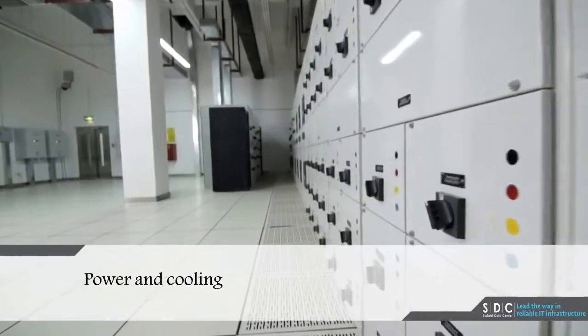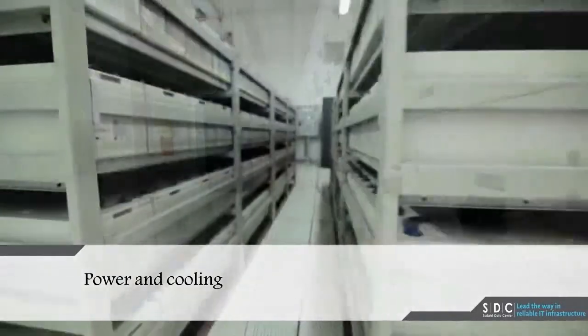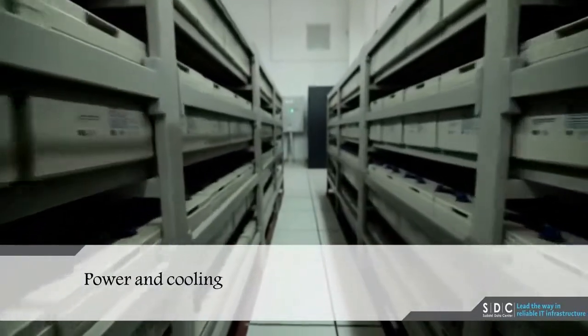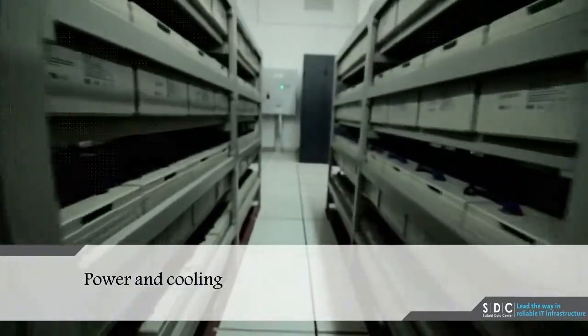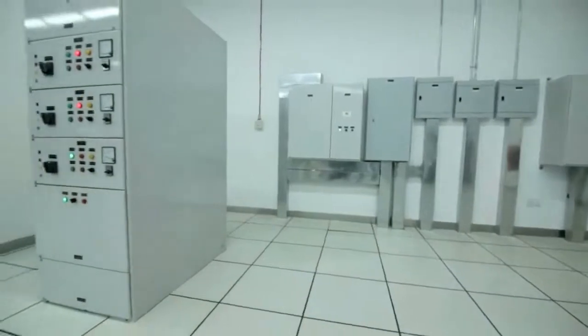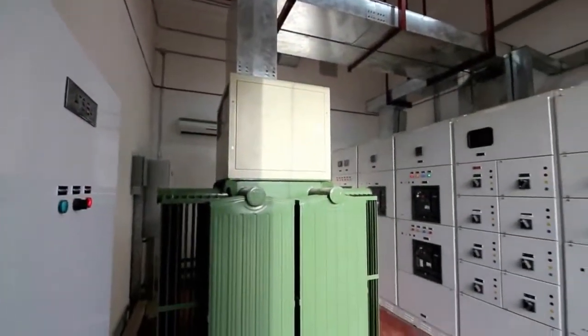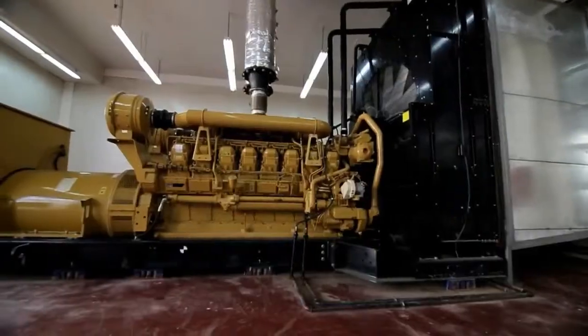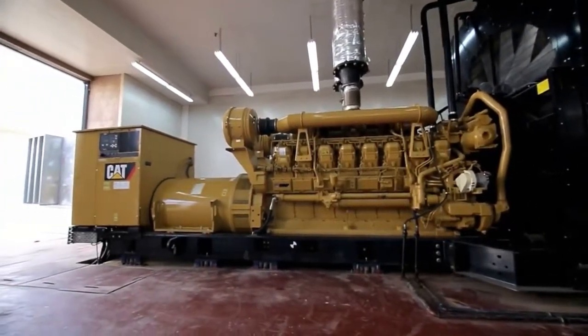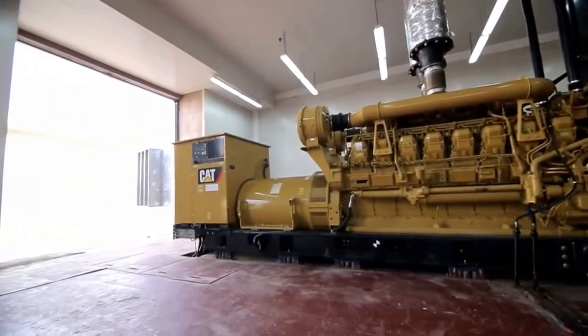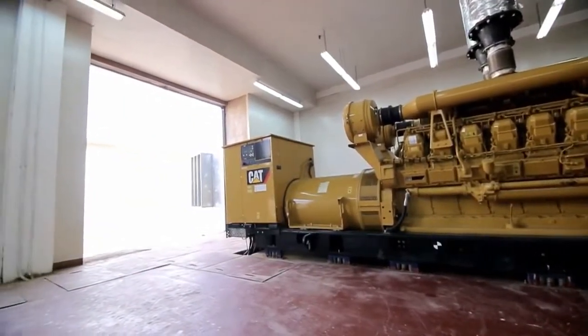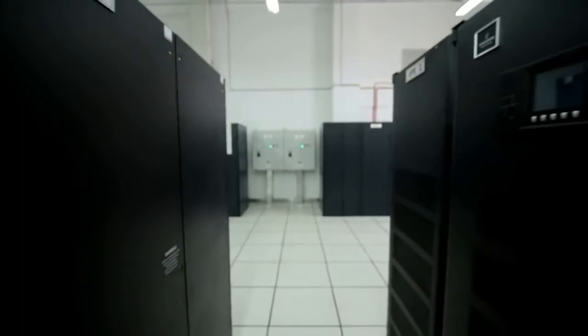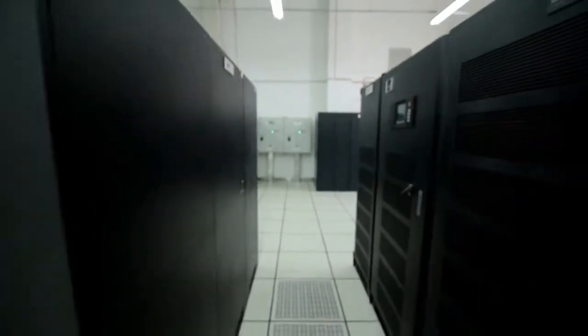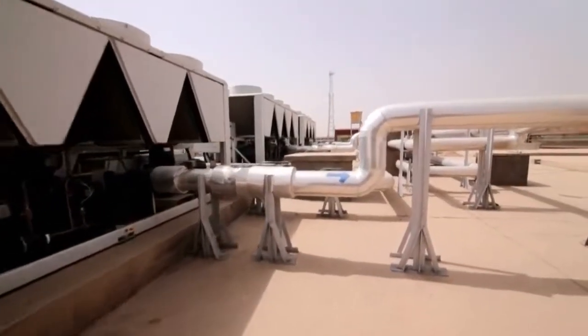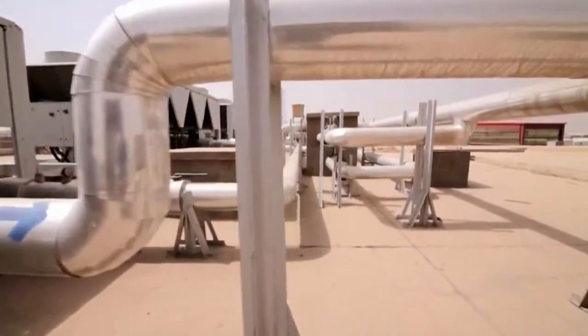Power and cooling. The center is supplied with various power and backup sources to ensure there are no power cuts, 2N+1. The center also has dual power supply lines with capacity 4 MVA each from 2 separate stations and a fuel tank reservoir with enough fuel to keep the center running at full capacity via diesel generators for 7 days, in addition to UPS and batteries which feed the sources.